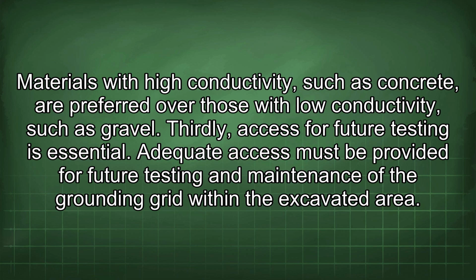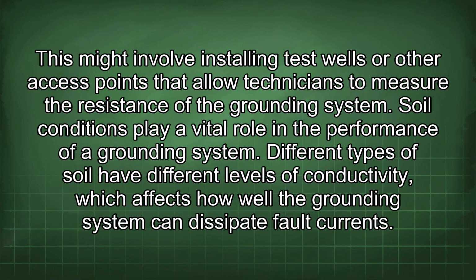Thirdly, access for future testing is essential. Adequate access must be provided for future testing and maintenance of the grounding grid within the excavated area. This might involve installing test wells or other access points that allow technicians to measure the resistance of the grounding system. Soil conditions play a vital role in the performance of a grounding system. Different types of soil have different levels of conductivity, which affects how well the grounding system can dissipate fault currents.